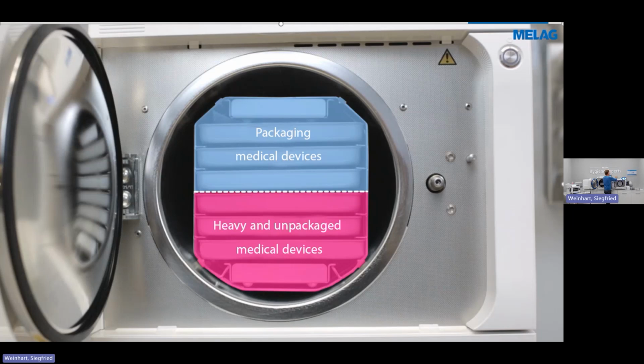And we see this a lot with hand pieces. So you might want to process your pouched hand pieces in there and then question whether you could actually run the loose instruments in there as well, the unpouched instruments. Well, the simple answer to that is yes, you can. Maximize the chamber. I see it a lot where practices will come in, they'll put 1 load of instruments on a tray, pop that in the sterilizer and then run it, okay? It's always the best thing to use the sterilizer to its full capability.